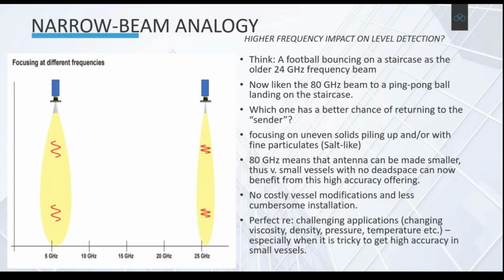What is the deal with newer radar, higher frequency? We've got 80 gigahertz now that you'll see for the LR100 range. In the past, they were 5 to 26 gigahertz, and some of the LRs are running at that frequency. They had a lower frequency but higher wavelength. Now they have obviously higher frequency and smaller wavelength.